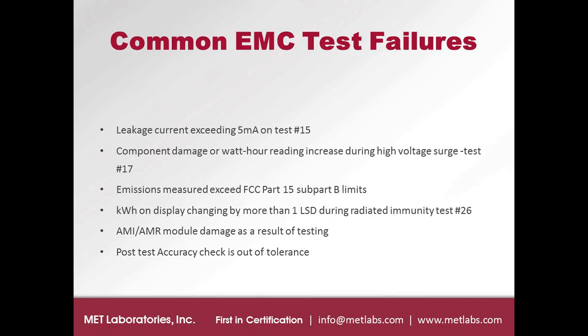We also see sometimes that the post-test accuracy check is out of tolerance, and we do see this happen sometimes during insulation test or surge test, wherein everything seems fine. The leakage current measured is in spec, it's less than 5 milliamps. The surge test, everything seems to go fine. The display does not change. There does not seem to be any obvious component damage. And when we try to perform the post-test accuracy check, that's when we discover that something is wrong because the accuracy check fails to meet the requirements.